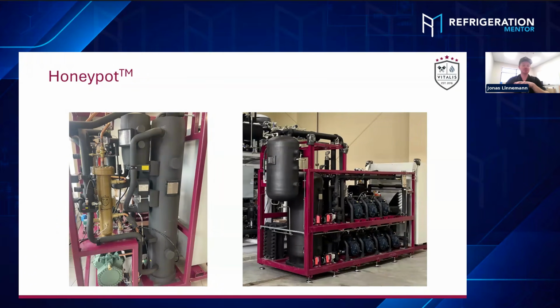Once you start the compressors up and they're actually running and pressure builds up, you will definitely have the differential pressure available for the oil reservoir to fill oil through the oil regulators. And then in the very first minutes and maybe the first hour, it's very good to keep an eye on the actual level inside the sight glass of the compressors. If the regulators stay green, fine. If they get yellow, that means typically they refill.